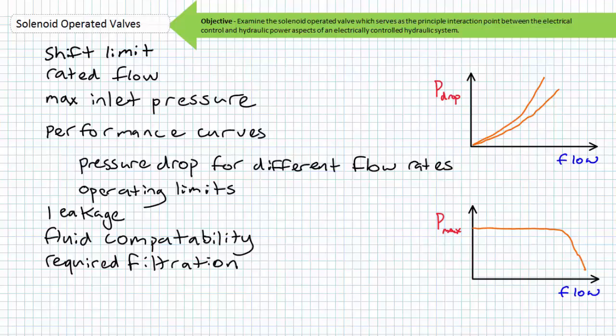The solenoid operated valve, like other hydraulic valves, typically have a rated flow and a maximum inlet pressure. The rated flow is a quick snapshot of this valve's performance at that flow rate. If you wanted to dive deeper into the valve's performance at flow rates other than the rated flow, you'd ordinarily consult the pressure drop for different flow rates performance curve or the operating limits performance curve. The pressure drop for different flow rates performance curve shows the typical restriction pressure drop created by the valve at different flow rates.